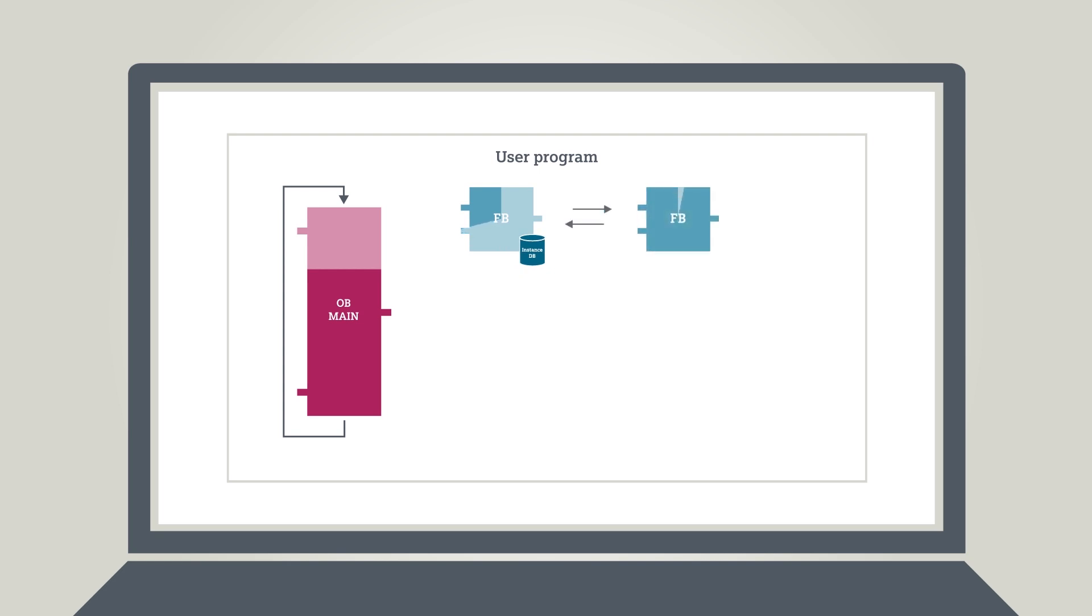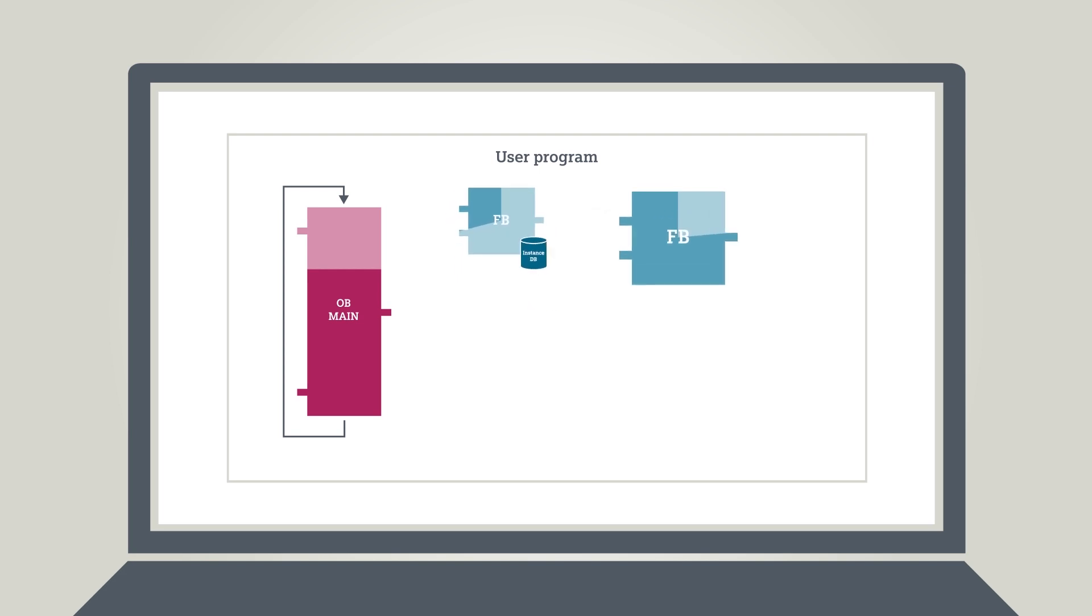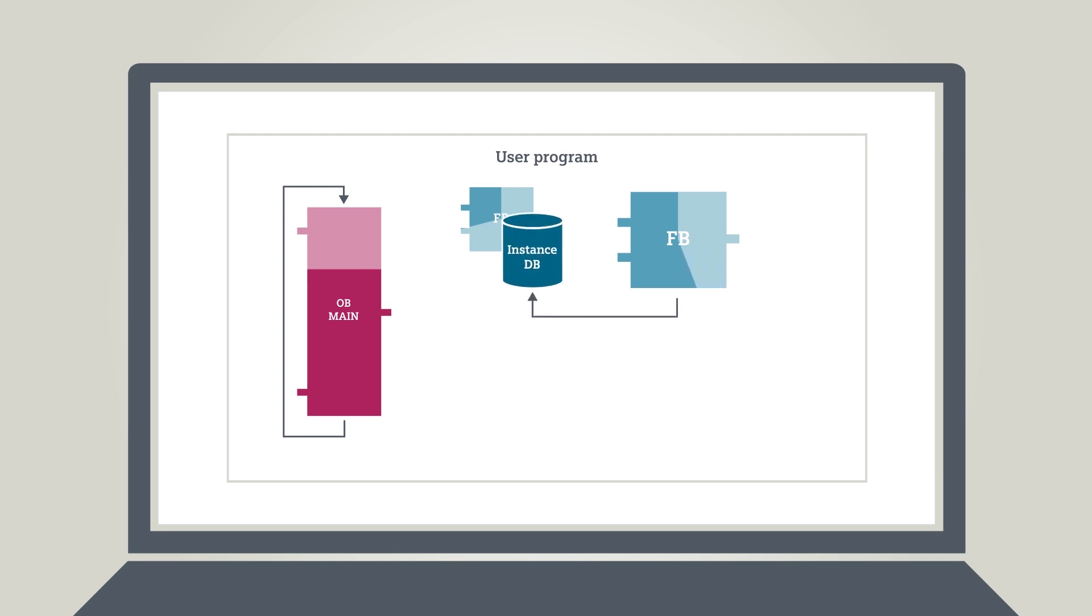Calling up FBs from within other FBs, interleaving, means that you can do call-ups as single or multi-instances. An FB called up as a multi-instance will store its data in the instance data block of the calling FB. This makes it easier to reuse that FB.